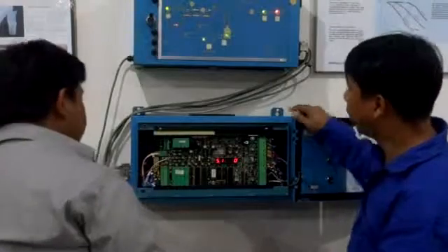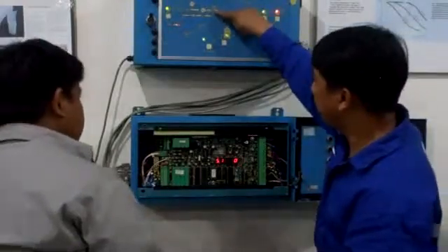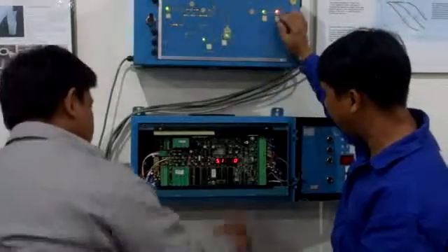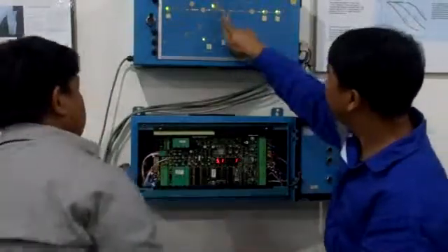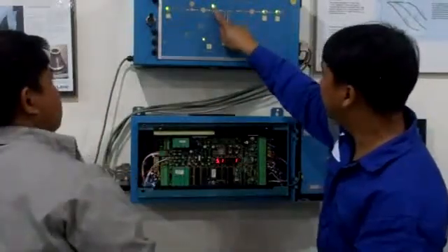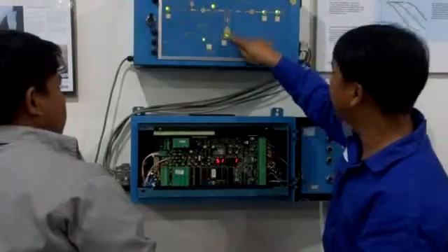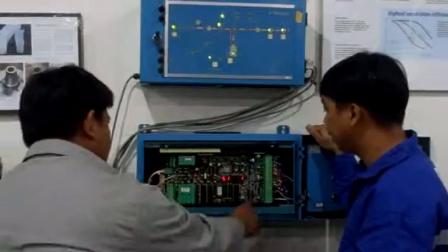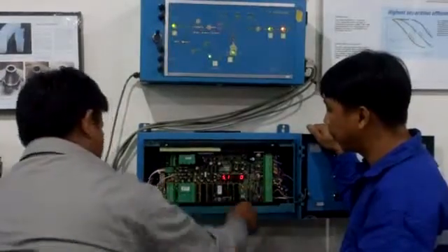Oil feed. Oil feed, that means that the three-way valve is going to feed to the separator. Okay, activate. Push button 3. So it will open the three-way valve, then the oil will go into the separator and then going out. Okay, next. That means our three-way valve is working.